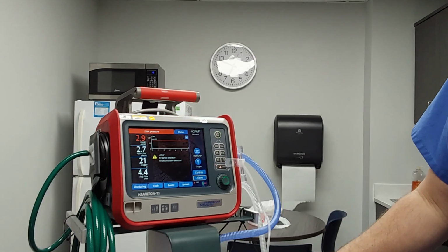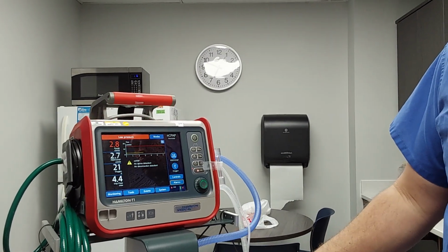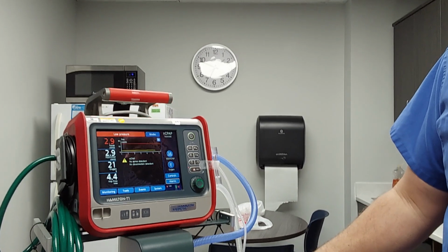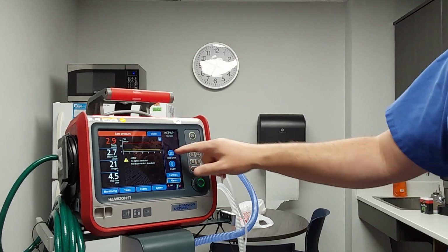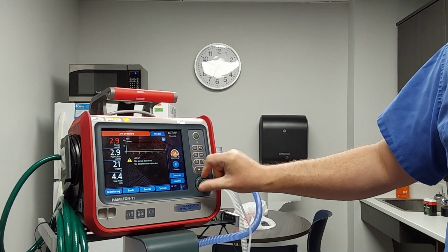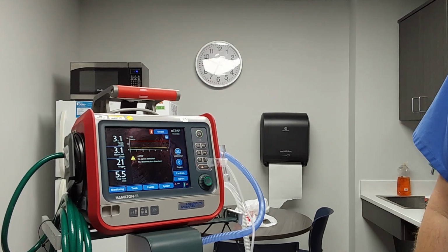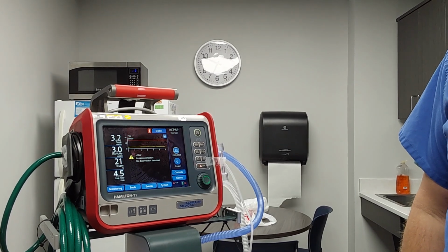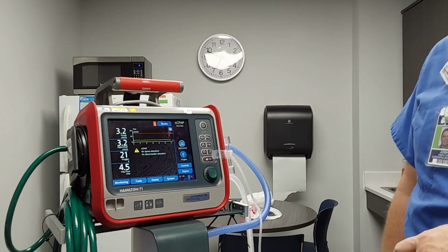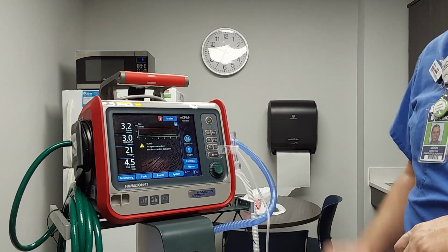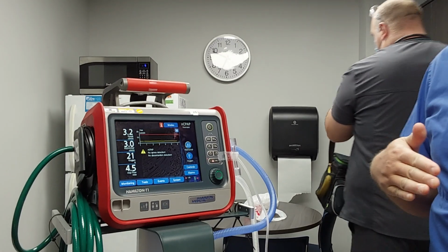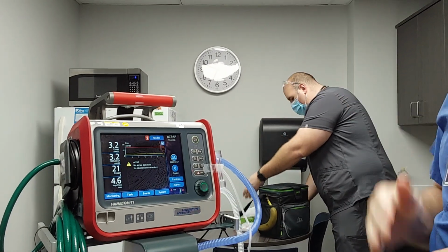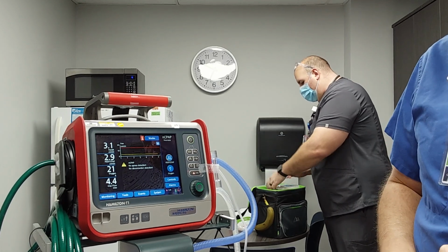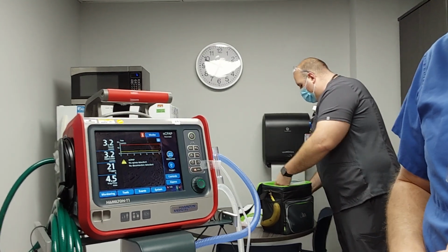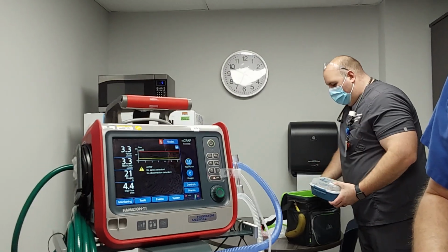No. What do they generally start them off at usually? I would start them at 5 or 6, or anywhere in between there. You can do half increments here too, like 5.5. FiO2 as well, lowest FiO2 to maintain your SpO2. So don't start at 100 and work backwards. Go the other way. Start low and work up with kids. Do you have to change out the circuit as far as anything different than from the ventilator, or does it all stay the same? All the circuit stays the same. The only thing you change out is the flow sensor.